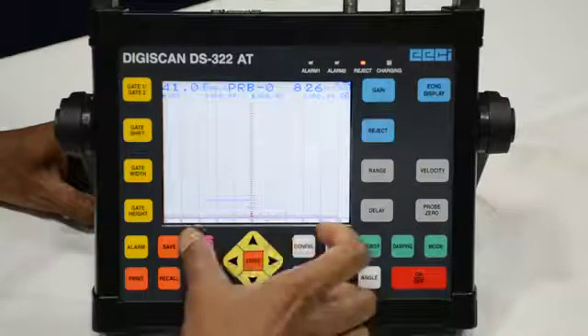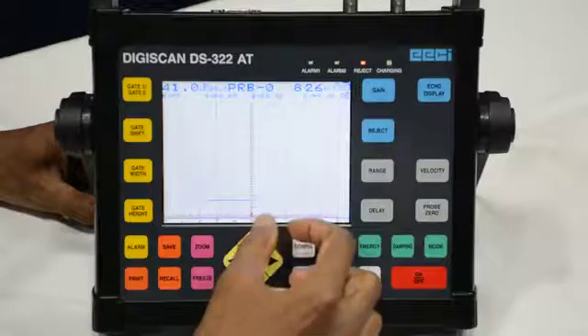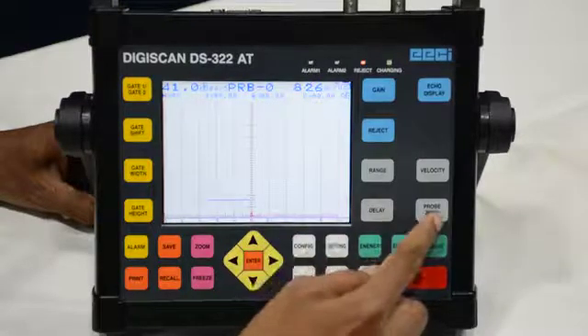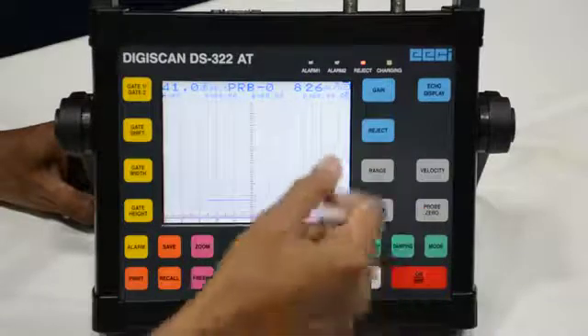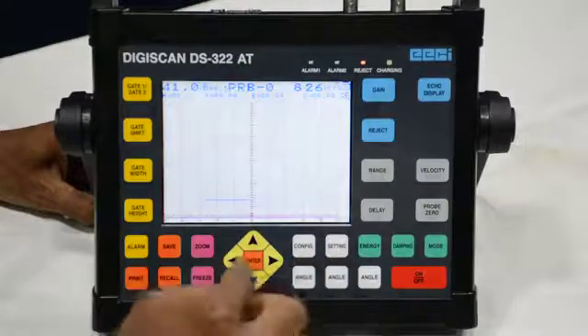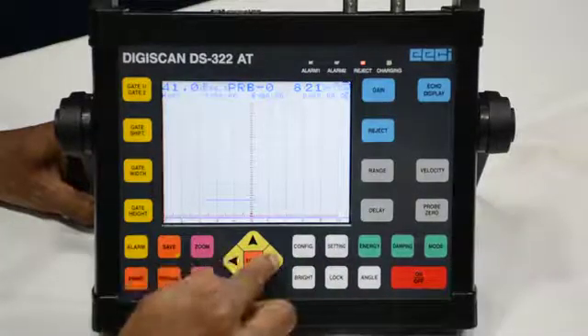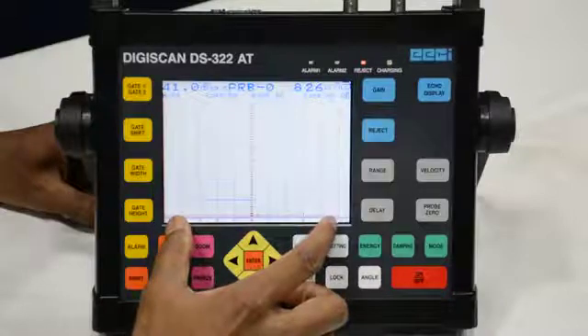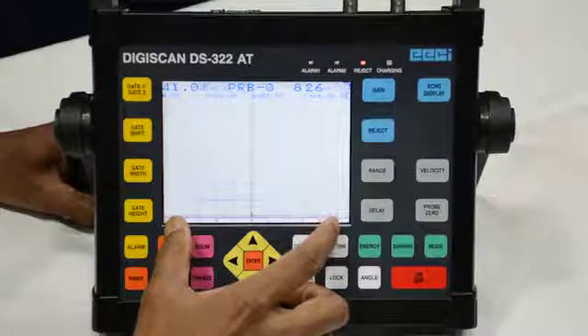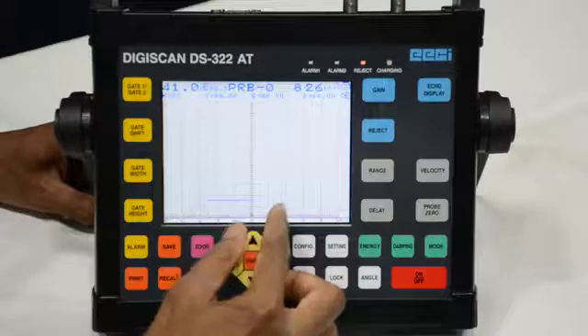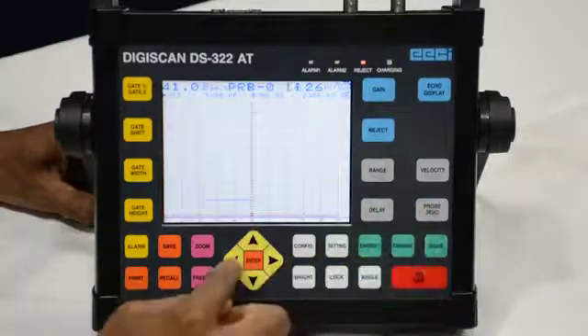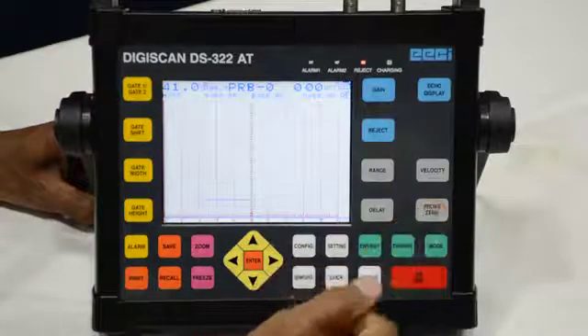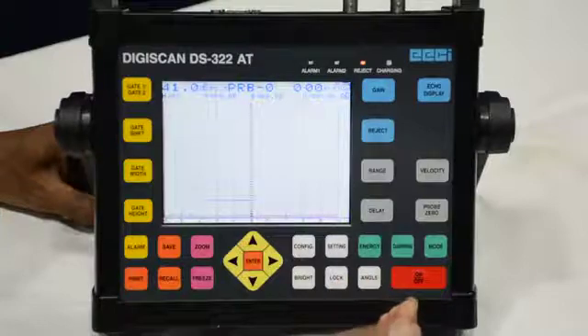If any echo is appearing on the screen and it is not at the proper location, we have to move it to the proper location. For that, this is the Probe Zero button. By pressing it, the time is shown in microseconds on the X-axis. We have to make it more or less as per our requirement. If we push again it will increase or decrease rapidly in a coarse manner. We need to make it 0 first.